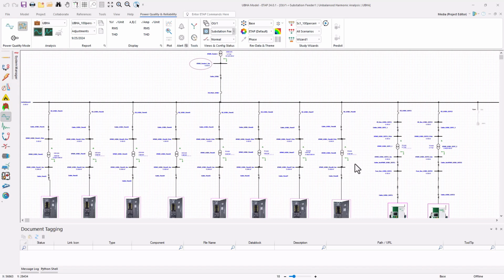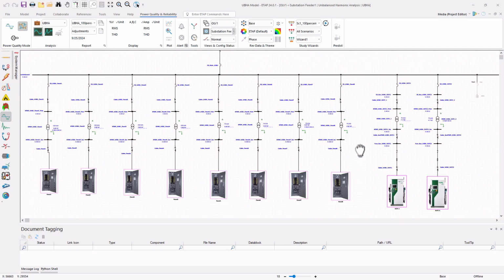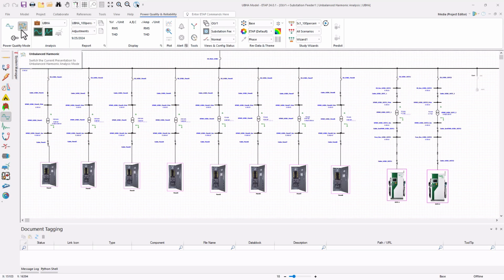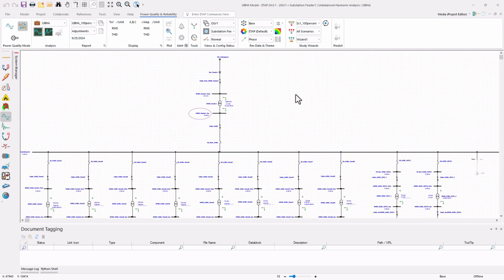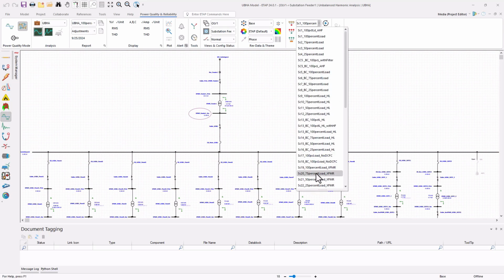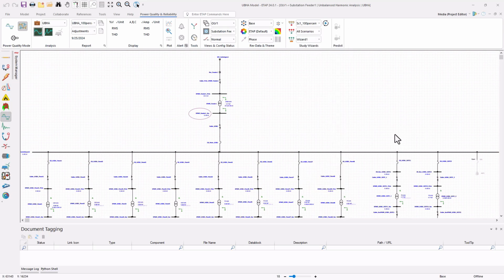As part of our engineering services, our team at ETAP Dynamics Division performed an unbalanced harmonic analysis study for a client. The project included multiple sites with electric vehicle charging stations that had level 3, that is DC fast chargers, and level 2 chargers installed inside these panels here. The objective was to assess the overall system response due to harmonic distortion introduced by the EV chargers installed in the sites, and to determine system configurations and conditions that cause voltage or current harmonic distortion to exceed the limits established by industry standards such as IEEE 519/2022.